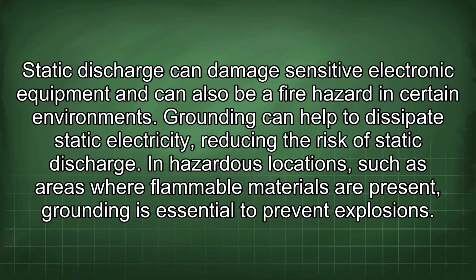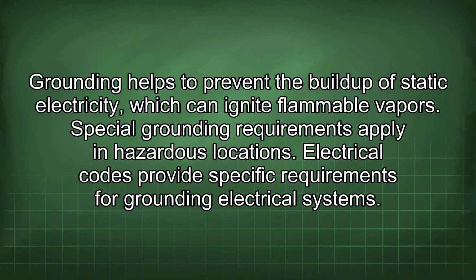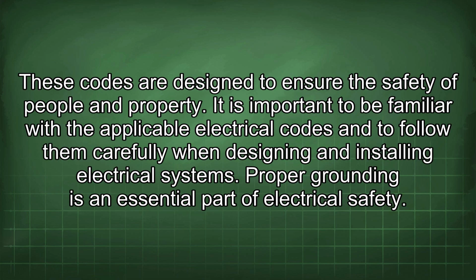In hazardous locations, such as areas where flammable materials are present, grounding is essential to prevent explosions. Grounding helps to prevent the buildup of static electricity, which can ignite flammable vapors. Special grounding requirements apply in hazardous locations. Electrical codes provide specific requirements for grounding electrical systems. These codes are designed to ensure the safety of people and property.